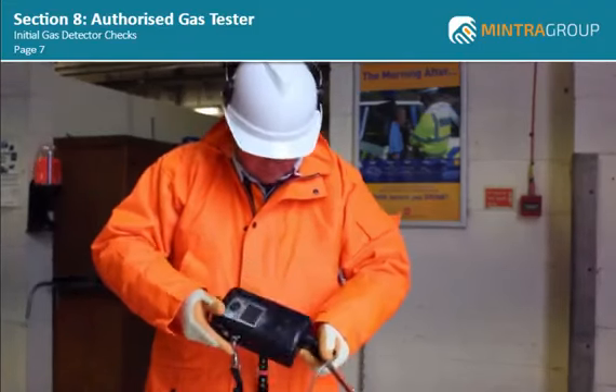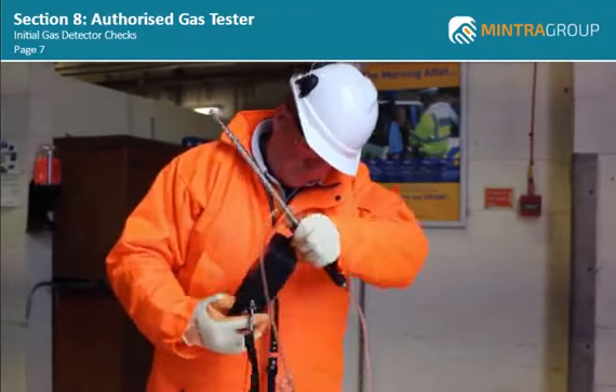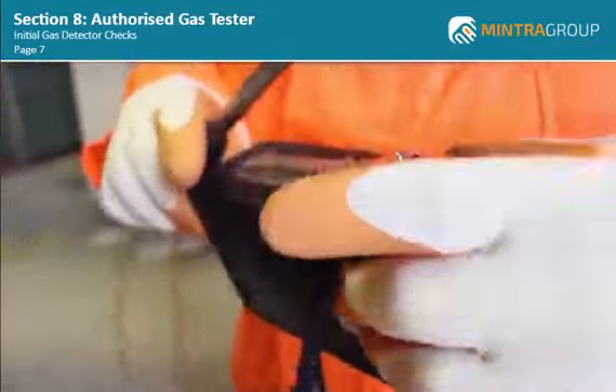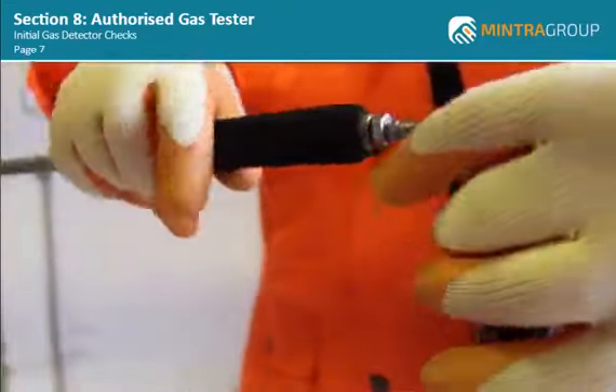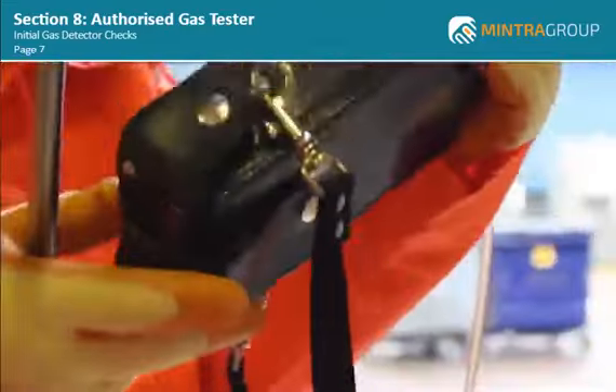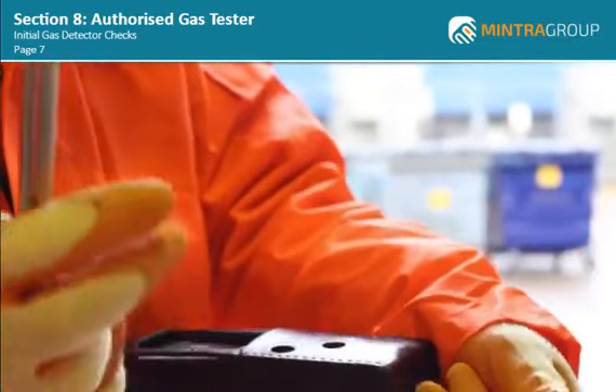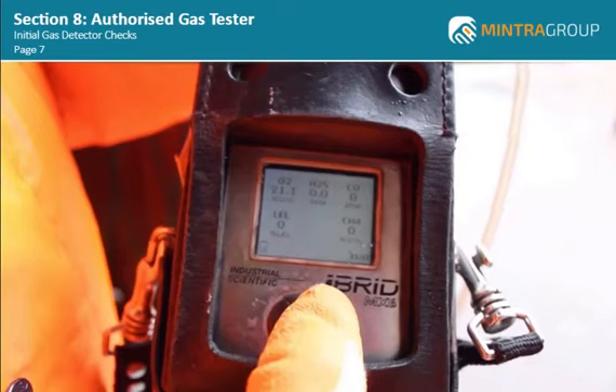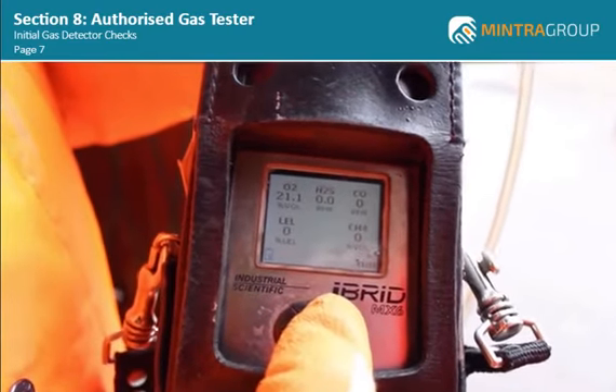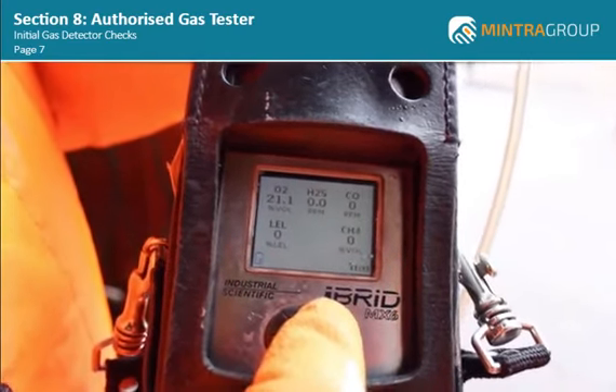The first check should be the physical condition of the gas detector. Is there any damage to the casing? Are there any cracks on the screen? Is the probe nozzle clear, and is the hose in good condition? If there is a water trap fitted to the probe, is this empty and dry? If the detector is damaged, you should report the damage to your supervisor as soon as possible and immediately remove the detector from service.